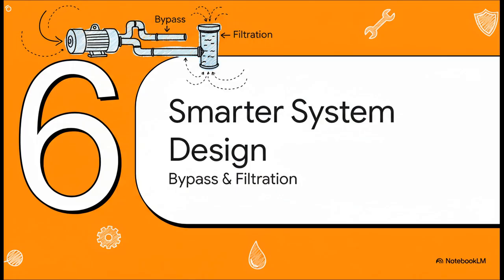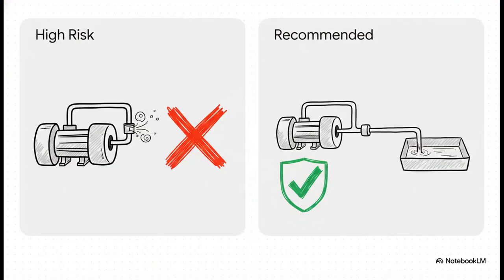Okay, those rules are a fantastic start, but protecting the pump really is a team effort. We also have to look at other parts of the system, like the bypass piping and the whole filtration strategy. Okay, just take a look at the bypass piping. A really common mistake is to pipe the bypass directly back into the pump's suction line. This is super risky because it can create a low pressure point that literally sucks air into the system through any tiny leak. The much safer recommended design is to send that bypass water back to the tower basin. It's a simple change, but it completely eliminates that risk.